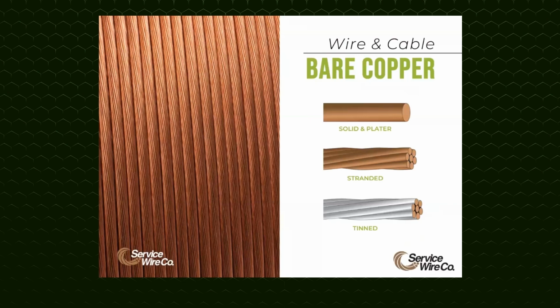ServiceWire's bare copper is available as a bare conductor or as an insulated conductor. We offer 3 forms of bare: solid, stranded, and tinned. Bare copper is essential in the correct operation and grounding of the electrical system, maintaining power and protecting people. System grounding helps detect and clear ground faults, provides a return path for ground fault current, prevents the buildup of static electricity, and more. All of these are key to keeping people and equipment safe on the charging site.